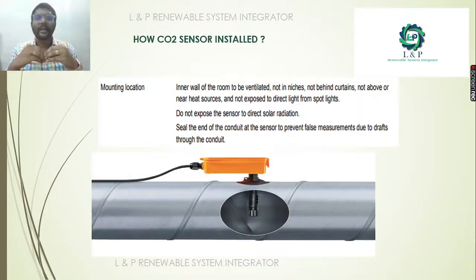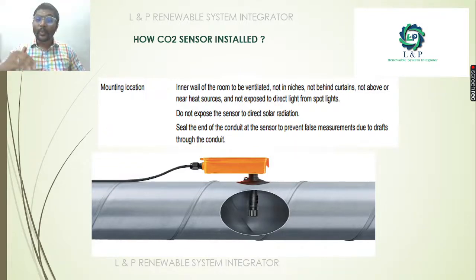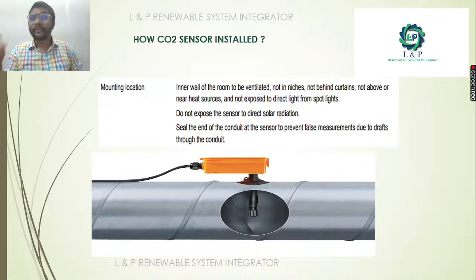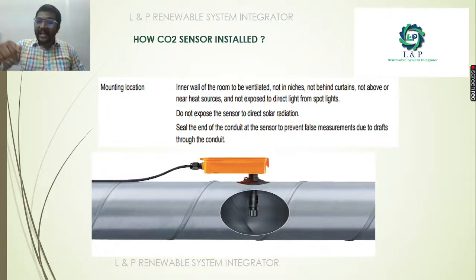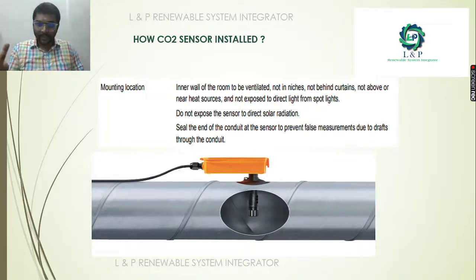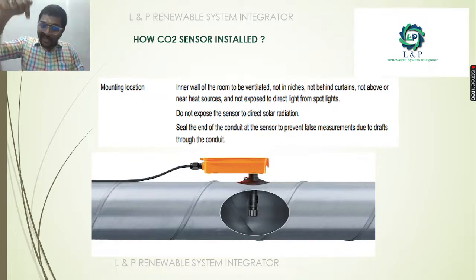Mounting is very much important. If you plan to mount inside a room, there should be enough ventilation. We should not install the sensor behind curtains, near any heat sources, or expose it directly to light. Even installing a sensor directly under a spotlight can cause measurement changes. Most importantly, we should not expose it directly to solar radiation. If planning to install in a conduit, to prevent false measurements due to draft, we need to seal the conduit. Also, if installing in ducts, please close the ducts properly to avoid false measurements.